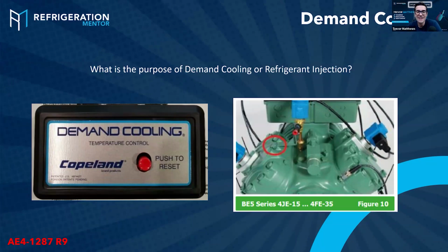It's been a while. But the thing is, all of a sudden we're going from 404 to 448, 449. And this is even 10 years ago, that's what was going on. So they went to 448, 449. Now 448, 449 run hotter. The characteristics of the refrigerant run hotter than 404, but not as hot as R22. So depending on the application, depending on the operation envelope of that compressor, you may have to add demand cooling or not. I get people that message me on Facebook all the time.